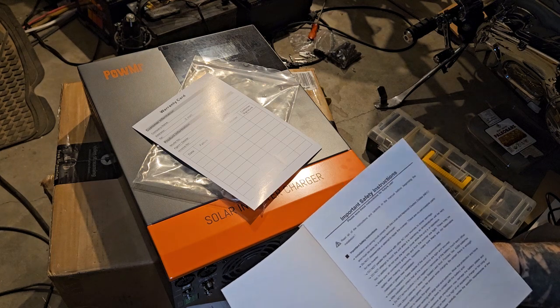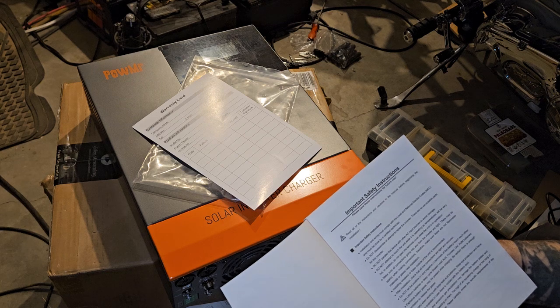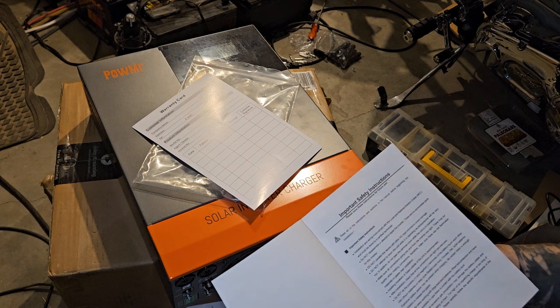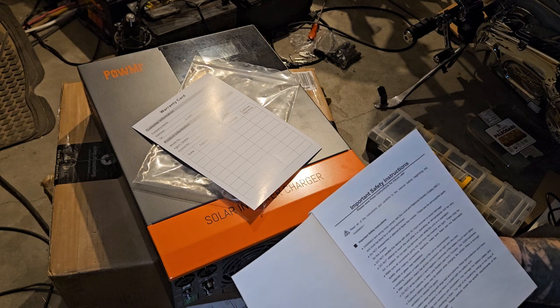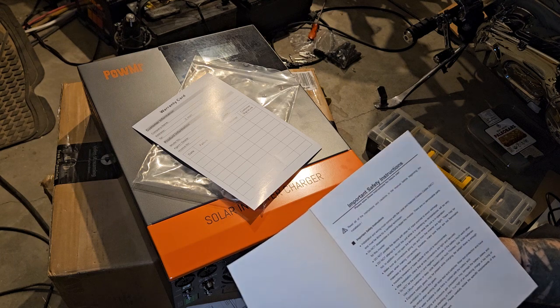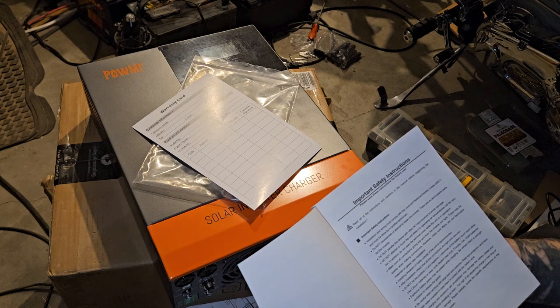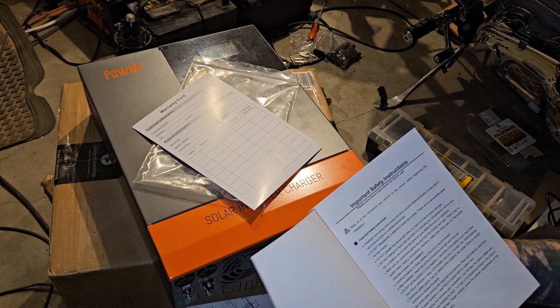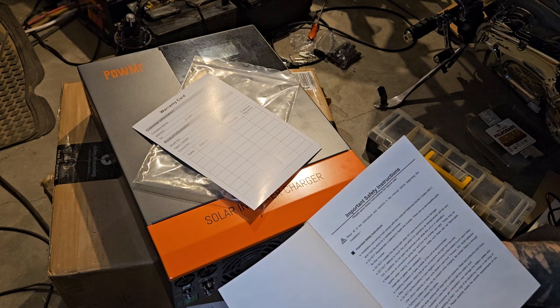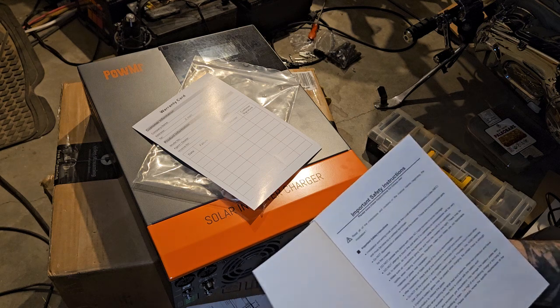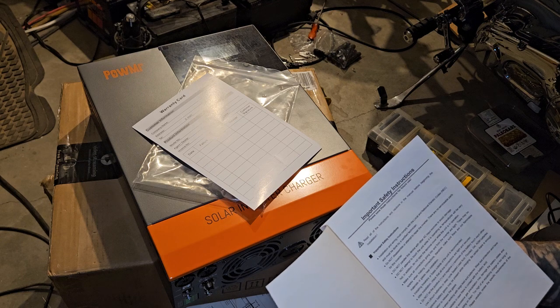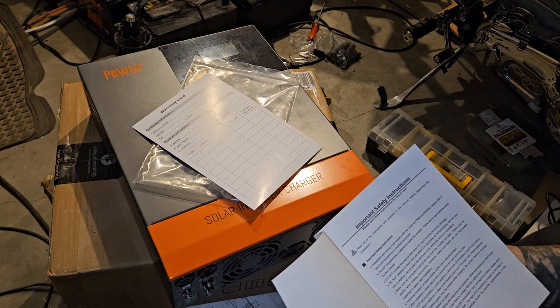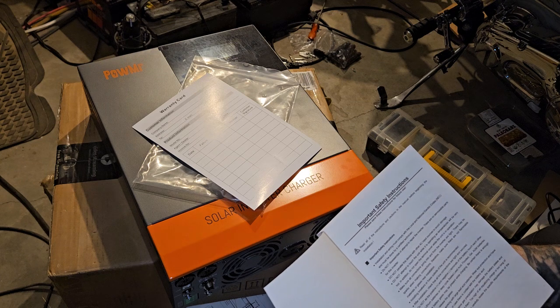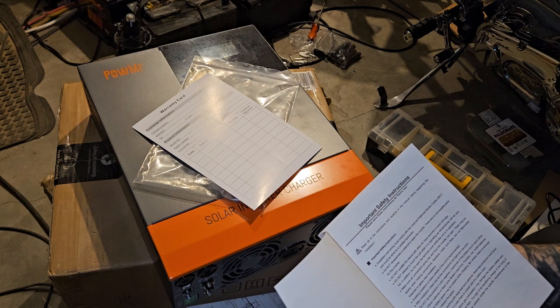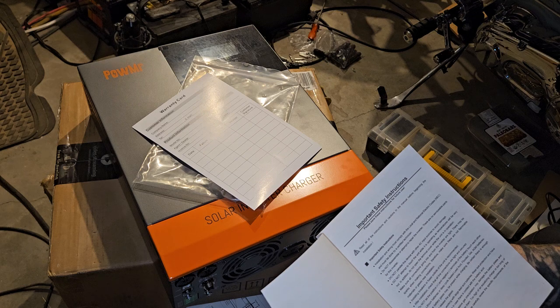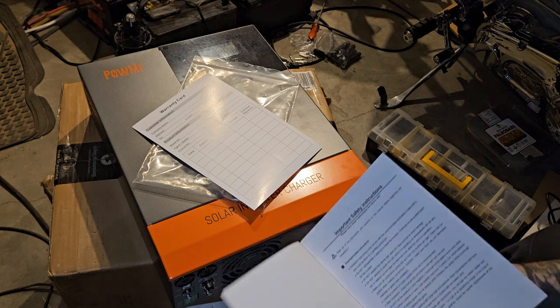Explosive battery gases, blah blah blah. Be careful when working with large lead acid batteries, or you might blow yourself up. Wear eye protection. Overcharging and excessive gas precipitation may damage the battery plates. Okay, never heard of that one before. Precipitation. It's raining inside the battery. Too high of an equalizing charge or too long of one may cause damage. Please carefully review the specific requirements of the battery used in the system.